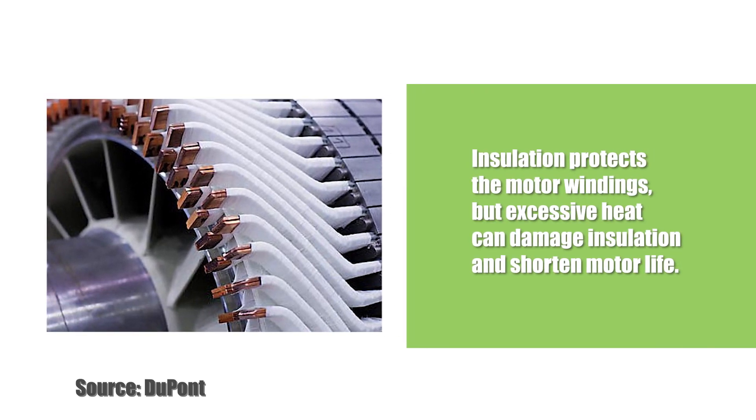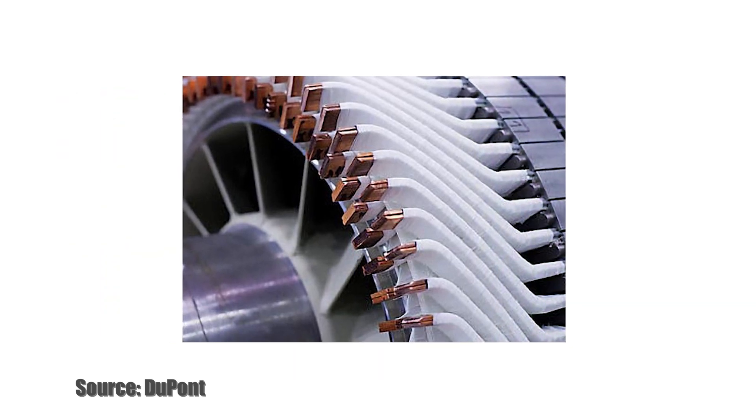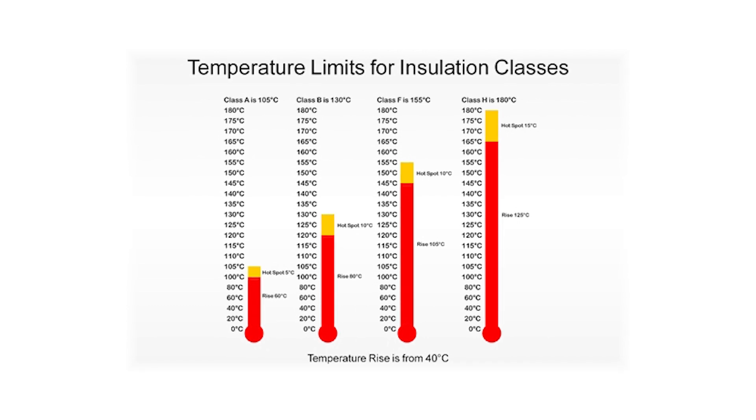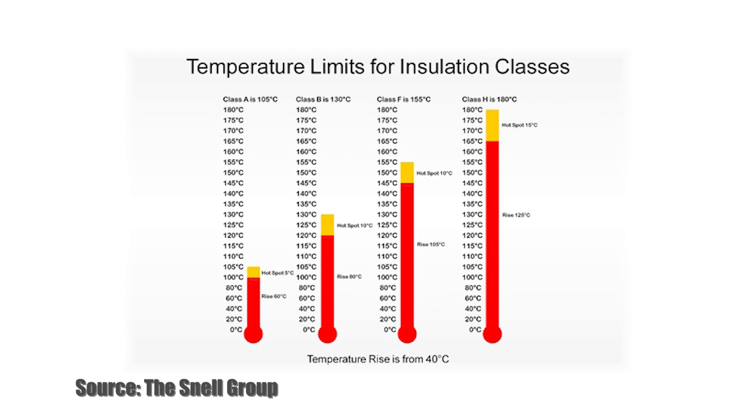To address the potential for failure of the insulation due to heat, the NEMA MG1 standard establishes four classes of motor insulation, which define the insulation system's ability to endure a specified temperature while providing a specific operating life. The NEMA insulation classes specify the maximum allowable temperature of the motor winding insulation under continuous operation that will provide a life of 20,000 hours.